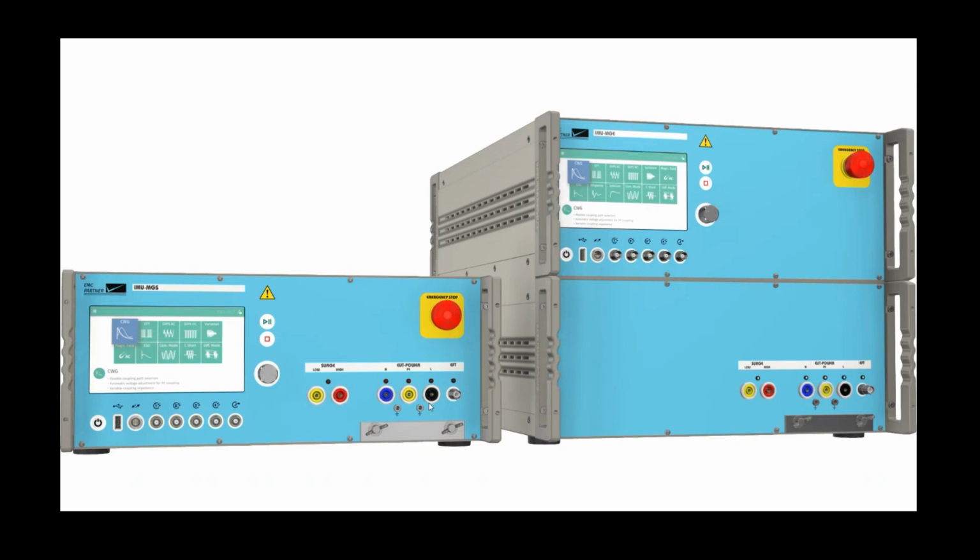The CDN couples the surge pulse or EFT burst onto the device under test power lines, but also decouples the pulse from traveling back into the power grid. And then the EFT high voltage output, this is a SHV connector for external accessories like a capacitive coupling clamp or external CDN. And then over here, we have a little ground bar. This is just to facilitate a proper ground bond to the ground plane. It's required for EFT tests to have this bonded to the ground plane.